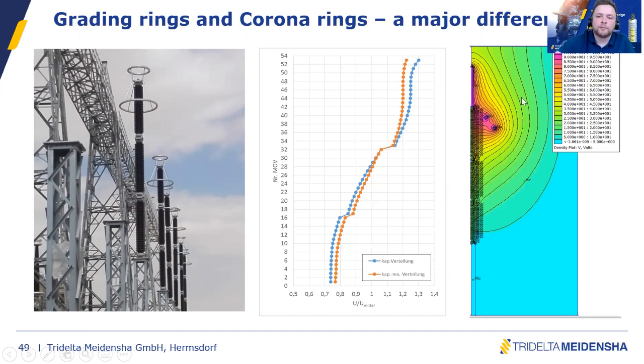The best situation is when the voltage stress is very even along the whole length and number of zinc oxide blocks. But this is only theory. In reality we can only improve this area here on top, and we will provide a stress that is maximum 1.2 of our voltage. That means that we will maximum apply the typical voltage ratio on this block, which we have on the whole surge arrestor, understood as continuous operating voltage. So this MOV block here on top can survive for the whole lifetime of the surge arrestor with the stress of maximum 1.2.